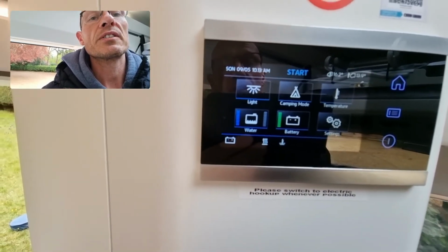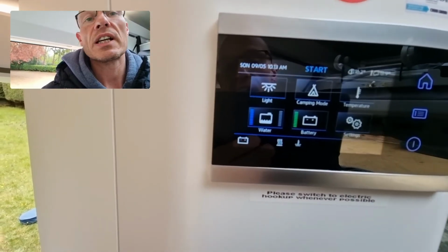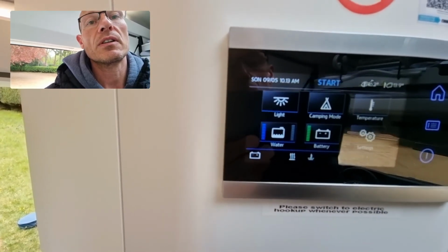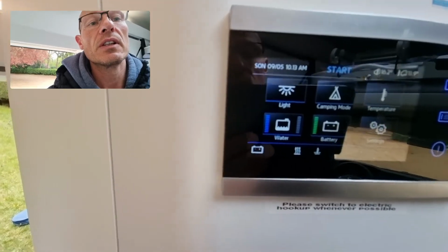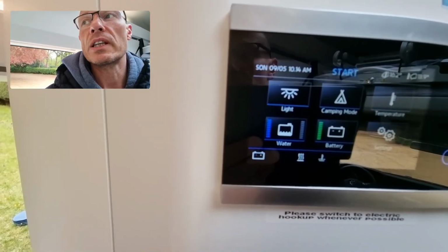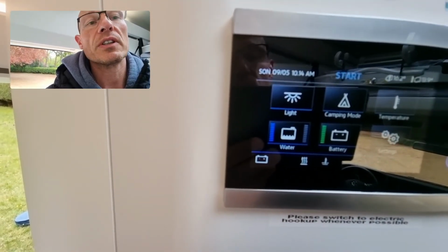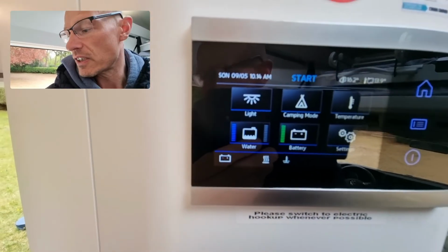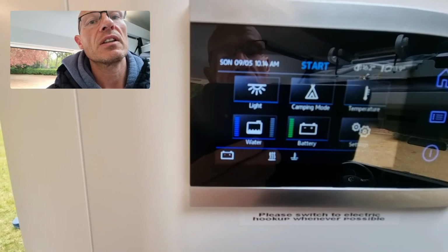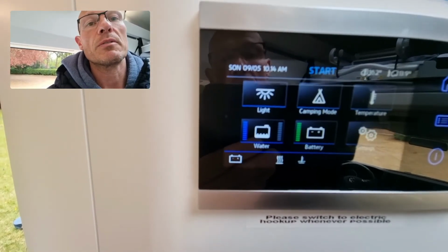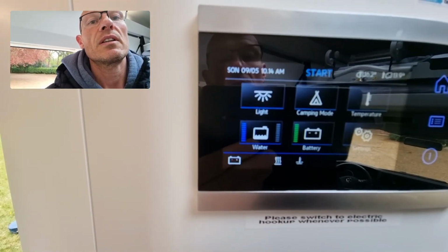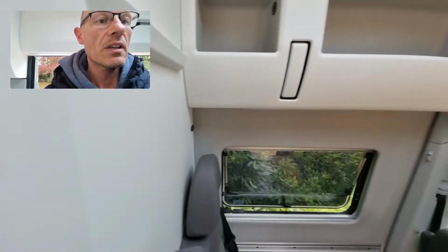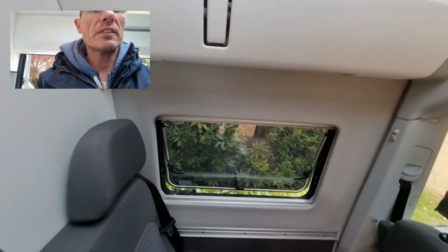Generally, the fault with the gas supply is either that the gas is not supplying from the gas bottles, and that could be because of the crash isolation switch, the yellow button, or it could be that the brass valves on the gas tap are closed, or it could be that the isolator valves underneath the kitchen sink have been disabled.